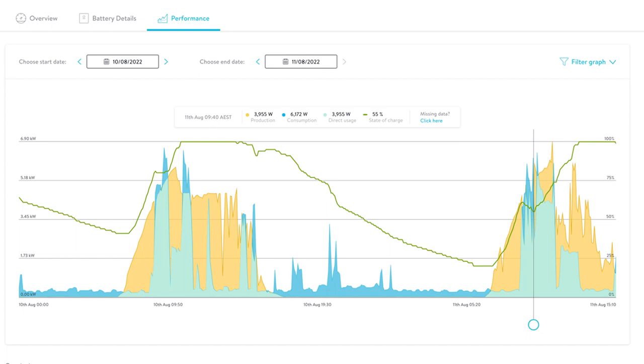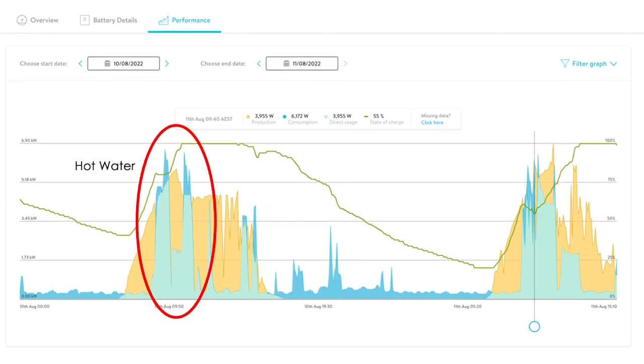The battery is 10 kilowatt hours full usable — you can drain it to zero — and you can also set a buffer of 5, 10, 15, or 20% for backup. Backup circuits typically include a powerpoint for the fridge or freezer, a lighting circuit, and possibly a modem — it can't back up high-consumption loads like air conditioning or an oven. It is a bit more expensive per kilowatt hour than other batteries in Australia, but the warranty, years in business, and Australian manufacturing tick a lot of boxes. Looking at our monitored example, in this instance the battery still had about 40% remaining at 7:30 a.m. when generation started — a lower-demand home. The battery reaches full charge by around 11 a.m. to midday even in winter, and the house runs fully self-sufficient from solar and battery through the day. Overall, we give the Sonnen battery an 8 out of 10.